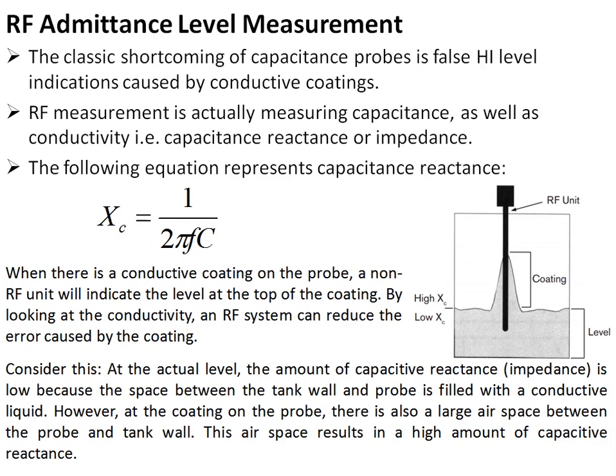At the actual liquid level, the capacitive reactance (impedance) is low because the space between the tank wall and the probe is filled with conductive liquid. However, at the coating, even though capacitance appears high, there is a large air space between the probe and the tank wall, resulting in high capacitive reactance. The electronic circuitry measures this high impedance in the coating area and counteracts the error caused by the capacitive coating, which would otherwise inflate the capacitance reading.